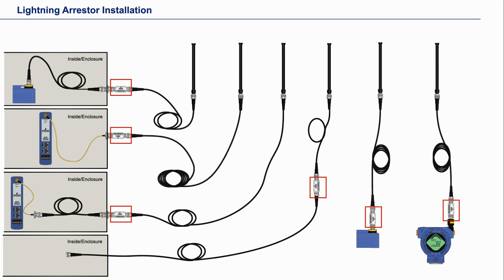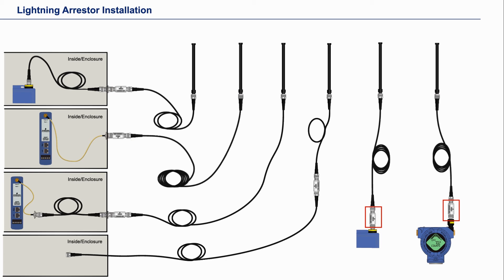Two general things to note: one, the lightning arrestor is always mounted outside. This is done to avoid a high voltage discharge indoors. Two, the lightning arrestor is mounted at the device or at the gateway when outside, and of course it is important that they are all grounded and sealed.